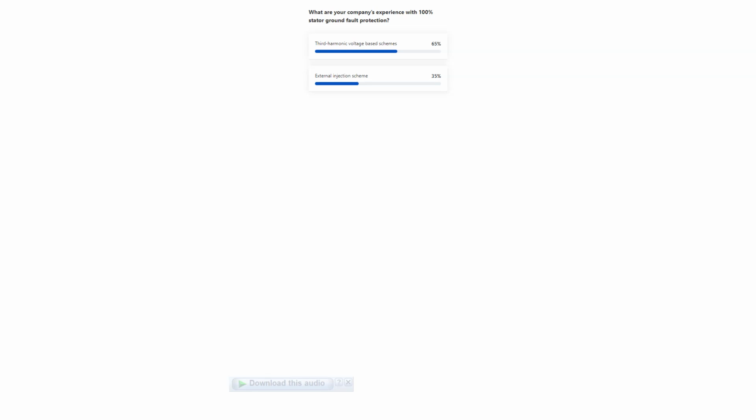Thank you. Yeah, this is within my expectation as well. Most utilities have attempted to do these third harmonic voltage-based schemes, but however, as I mentioned, the catch is that not every generator can generate enough third harmonic content for the user to effectively apply the third harmonic scheme, right? So that needs to be tested and verified in live field tests. External injection, some attendees seem to have experience, but this is starting to gain popularity right now, just due to the disadvantage of a third harmonic voltage-based system.